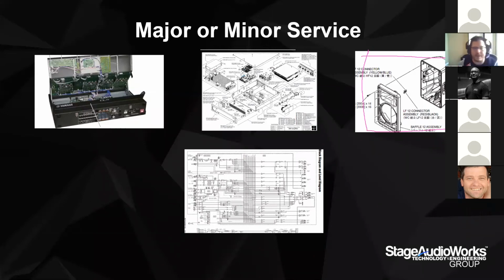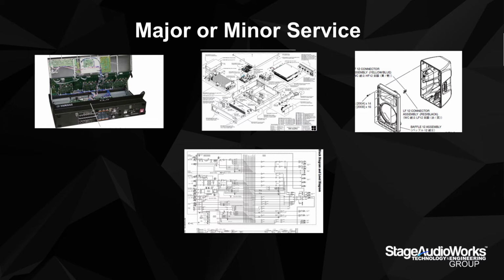And this is why for major services we normally have to get in. From a minor service perspective, if you look at projectors, lamps and filters will be user replaceable. If you look at anything else, like fuses, normally on most equipment there's an external fuse. If you have to replace the fuse, just look at the rating. But normally care instructions are inside of the user manual. So if those instructions are written inside the user manual, that's normally a minor service that the user can perform.